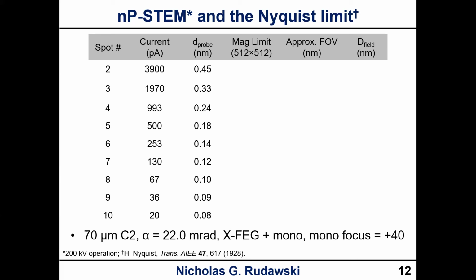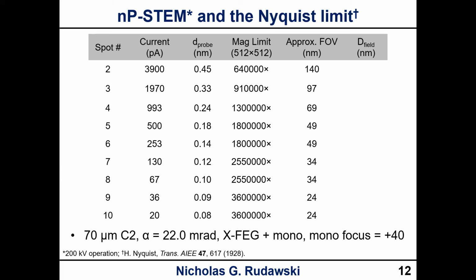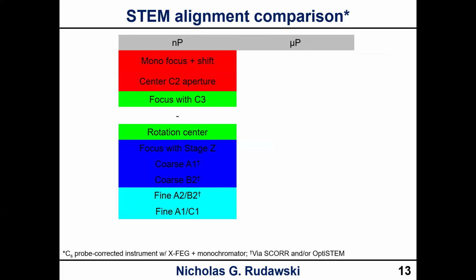Now, if we look at the mag limit, these are going to be a lot higher, of course, because your probe sizes are much smaller. And that gives you a smaller field of view. Our depth of field that corresponds to these fields of view is now much smaller, down around 10 nanometers or less. When you're up around several million X and you're in a field of view that's just a few tens of nanometers, your depth of field is literally just a few nanometers here. We're going to see how that impacts us in a minute.